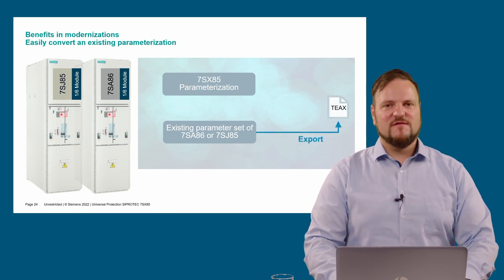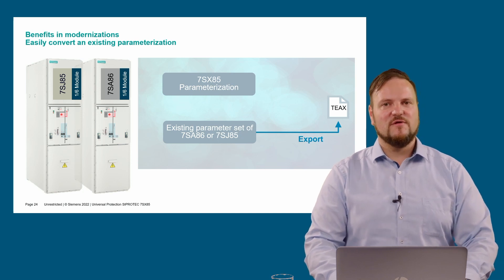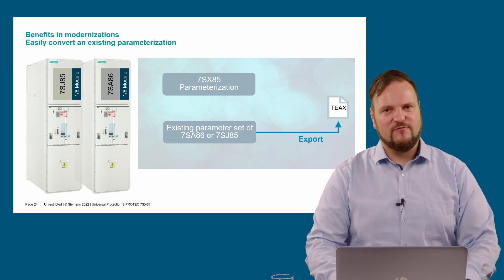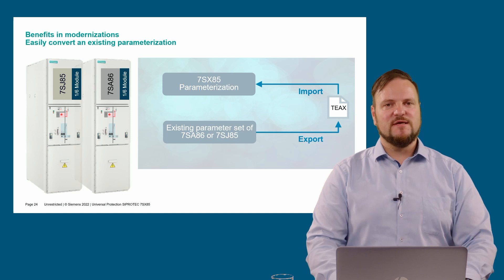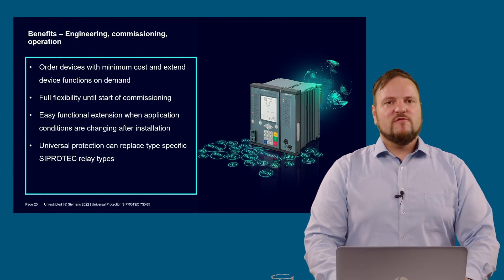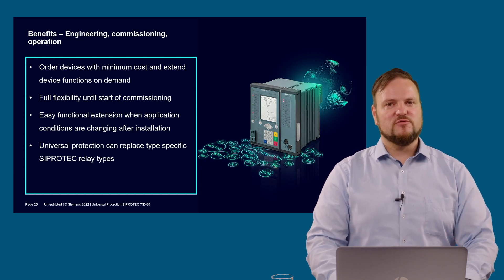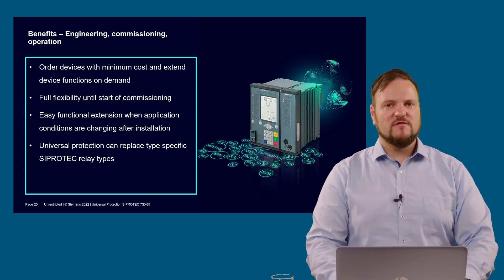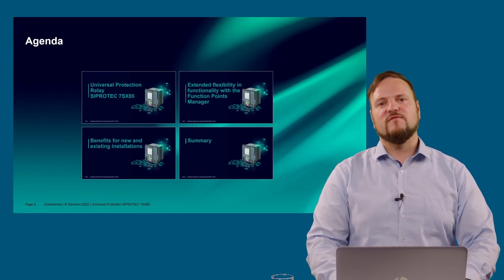The existing parameter set of the 7SA86 or 7SJ85 can be exported using the TotalIntegration Energy Exchange format — known as TIEX — and imported into the 7SX85 parameterization with just a couple of clicks. Device variety is significantly reduced, decreasing spare part numbers. Devices on stock have minimum functionality, reducing capital employed, while additional functions can be ordered on demand and paid for only when downloaded. The investment is kept as low as possible while maintaining full flexibility.